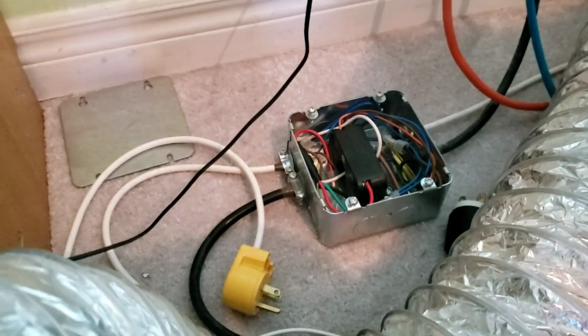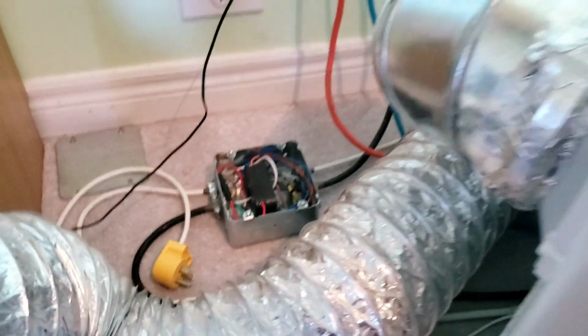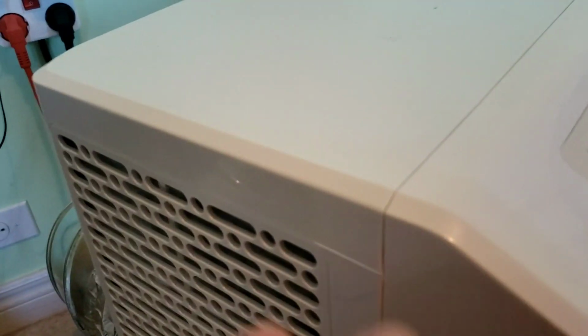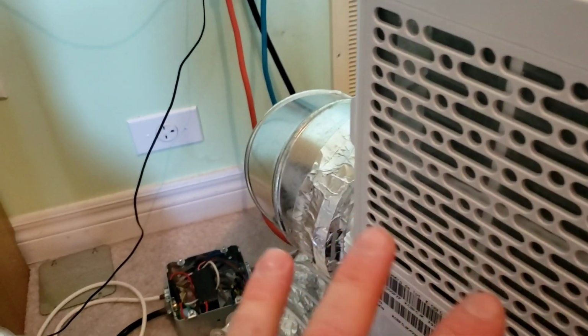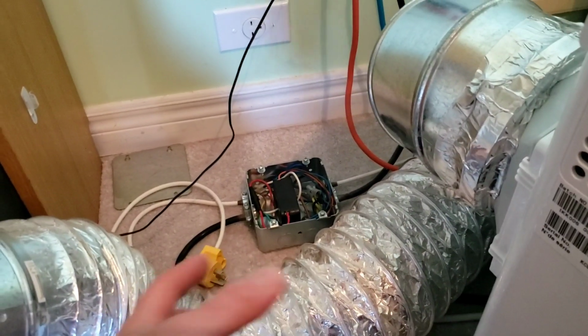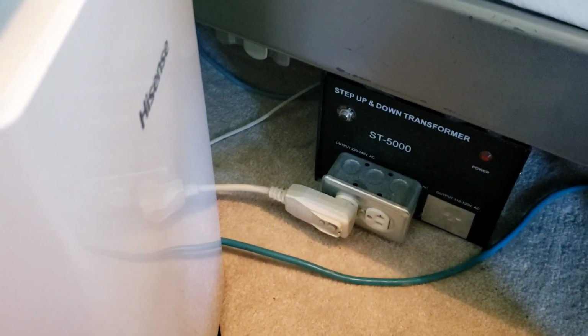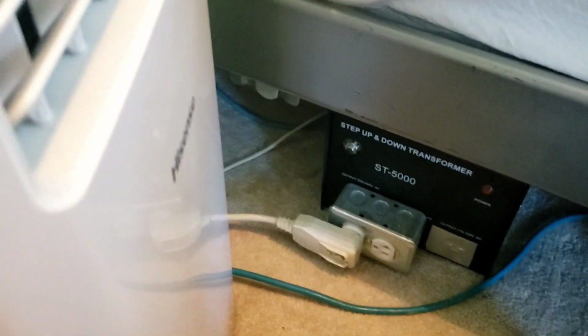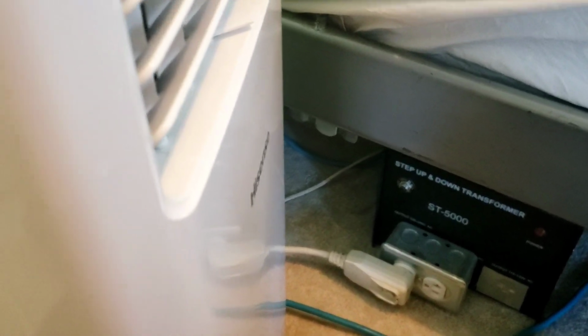So the way this is wired is, when you turn on the fan or the AC unit like this one while it's already unplugged, you turn it on and have a minimum of 5 amps of current going through one of them, it turns on both booster fans. If I plug in a vacuum cleaner that draws 1100 watts, it turns on the booster fans too, no problem, even if the AC units aren't on. That's what it is.